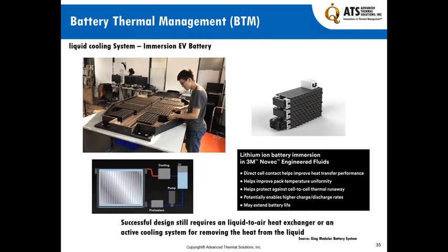Here's a concept done by, I think, Xing modular battery systems out of China, where they put the whole system into an immersion bath — this is what these systems look like. You obviously have to have a liquid-to-air heat exchanger to take the heat out, if you don't have that heat exchanger on top. But regardless, you have to have another heat exchanger further back to take the heat generated by the battery to make sure it's working properly.